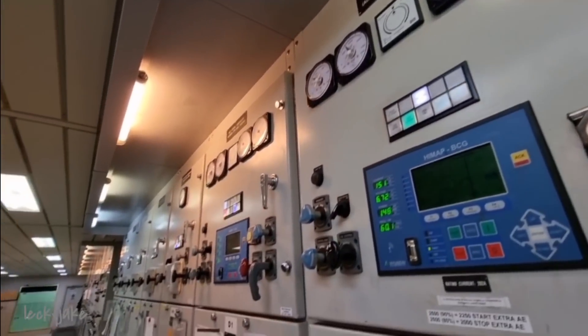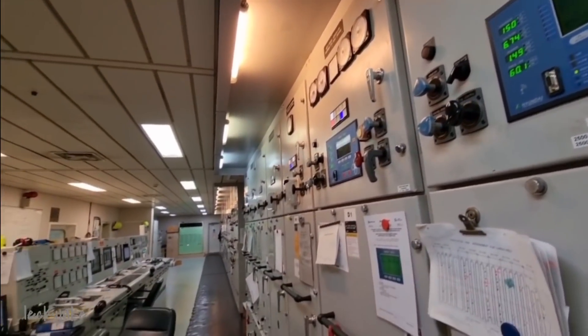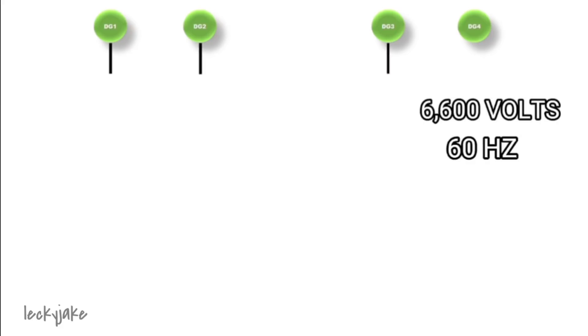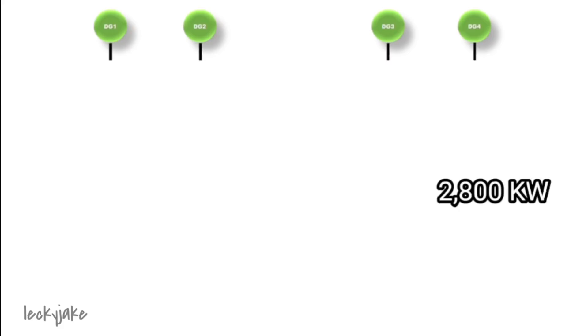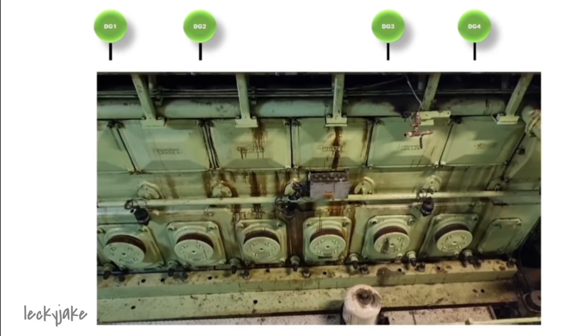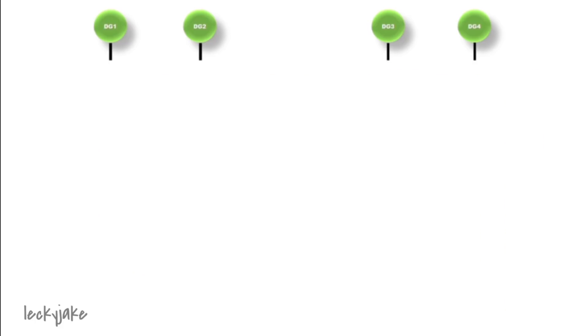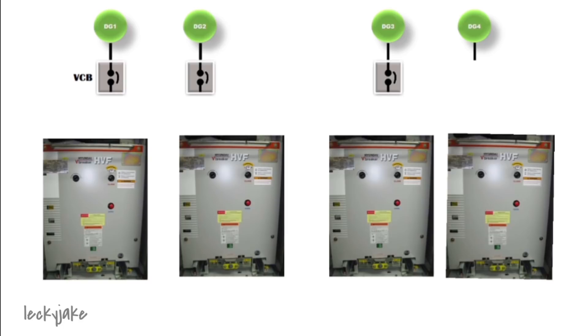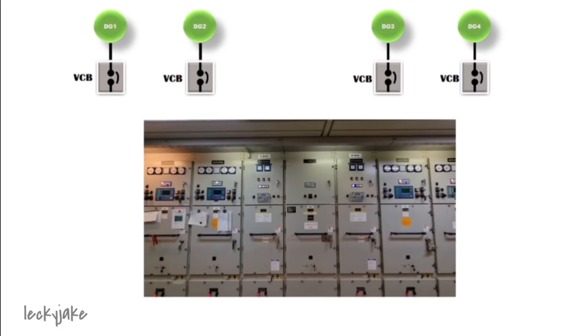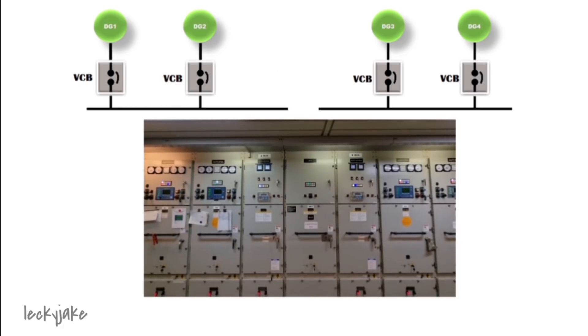So to understand it further, let's discuss this in a line diagram. We have four generators on board which supply 6600 volts at 60 hertz with a nominal load of 2800 kilowatts. This produced electricity will pass through individual vacuum circuit breaker first, and then these VCBs will be connected into the bus bar.